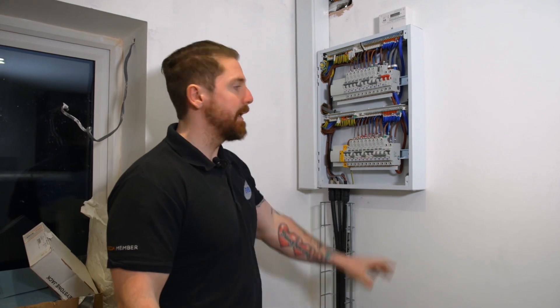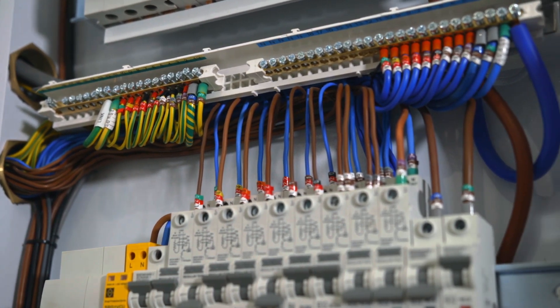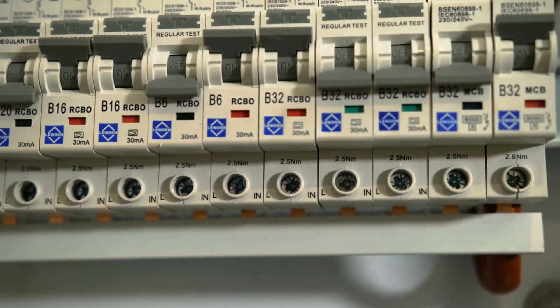We've switched over to see our main incoming board. This is again a Lewden board done by Mikey — absolutely cracking job. You'll notice it's all indented up and matches the drawings done by our CAD designer Danny. That means if we ever have any issues, or anything's removed or disconnected for whatever reason, we know exactly where it's supposed to be going. You'll also notice we have surge protection and RCBOs across the board. That's because it's a smart home with a lot of very sensitive equipment attached to the system, and in case of any fault we want to make sure everything is protected.